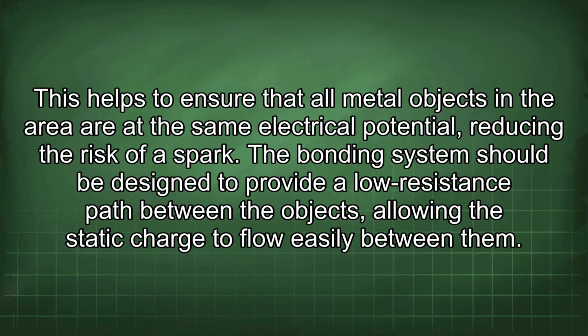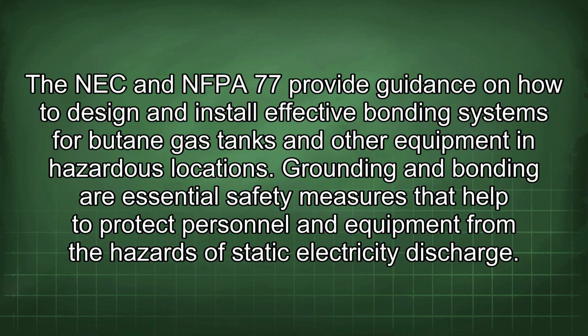This helps to ensure that all metal objects in the area are at the same electrical potential, reducing the risk of a spark. The bonding system should be designed to provide a low resistance path between the objects, allowing the static charge to flow easily between them. The NEC and NFPA 77 provide guidance on how to design and install effective bonding systems for butane gas tanks and other equipment in hazardous locations.